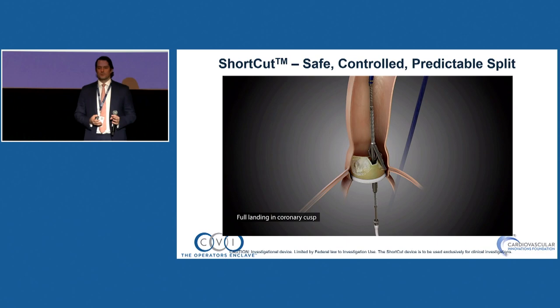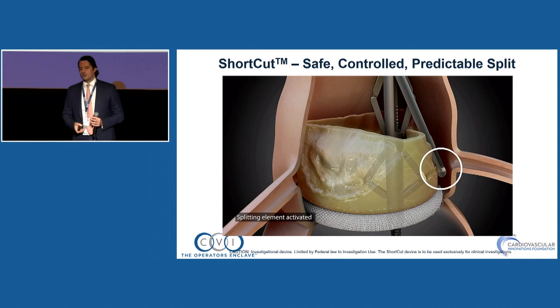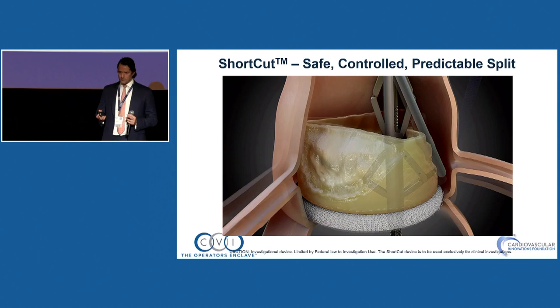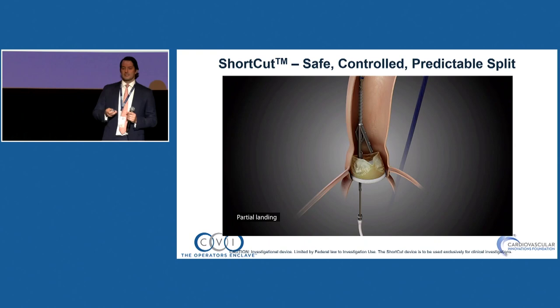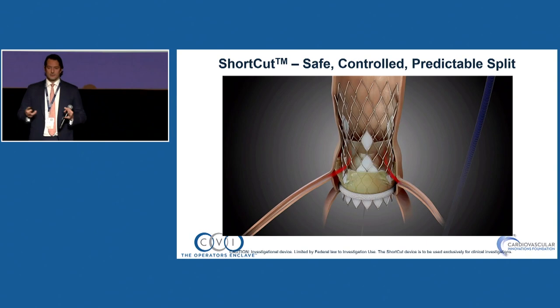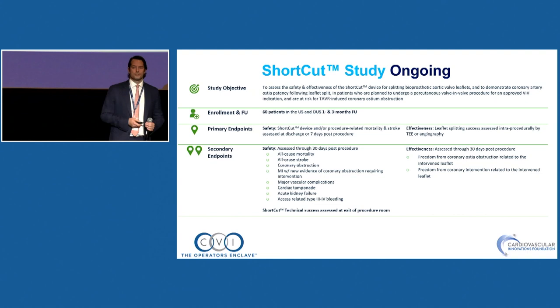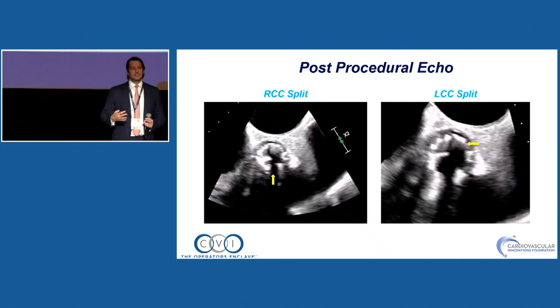The Shortcut device from Pi-Cardia is now under study in the U.S. with 60 patients, almost finished enrollment. It's a dedicated BASILICA-type device with a post and blade to split the leaflet in front of the coronary — a 16 French sheath and delivery system. We did a couple of cases at Morristown splitting one and two leaflets — it's a 15-minute procedure for both leaflets. You can see the dual split on imaging; it's very efficient and preserves coronary flow.